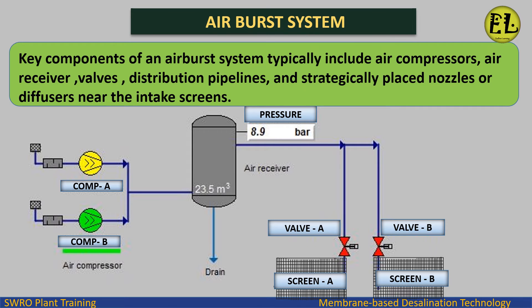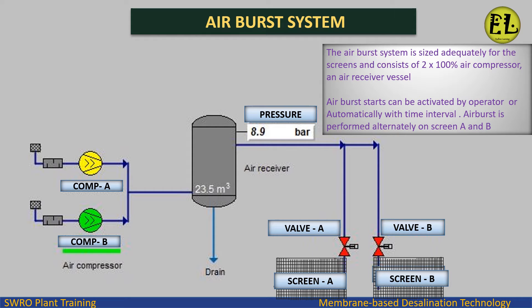Key components of an airburst system typically include air compressors, air receiver valves, distribution pipelines, and strategically placed nozzles or diffusers near the intake screens. The airburst system is sized adequately for the screens and consists of 2x100% air compressors and an air receiver vessel.